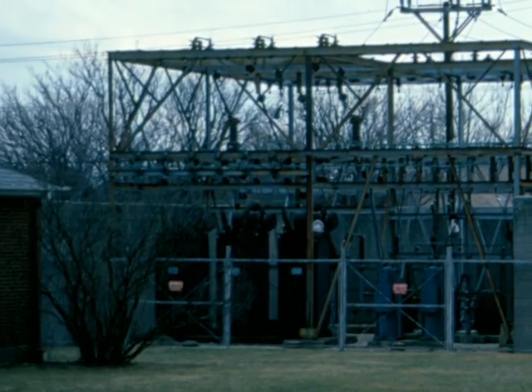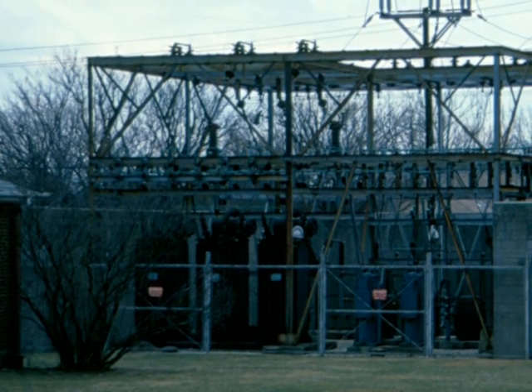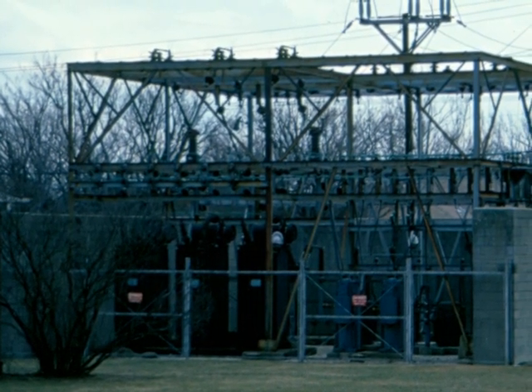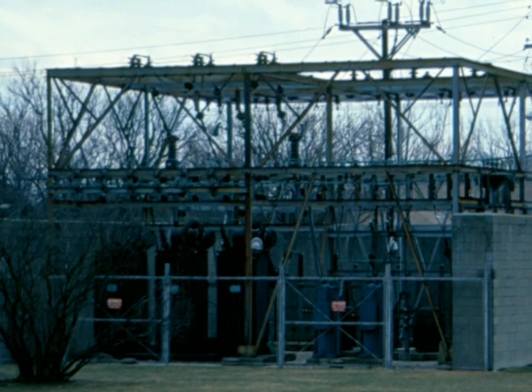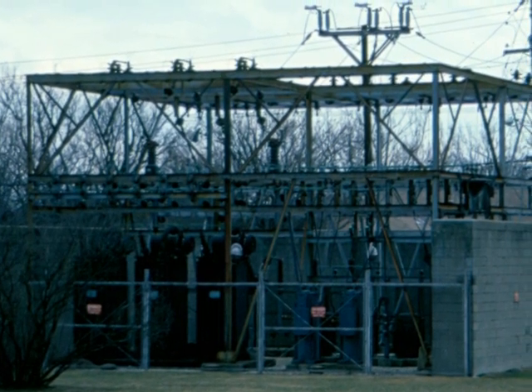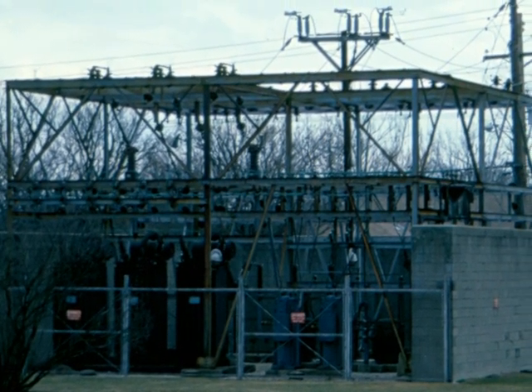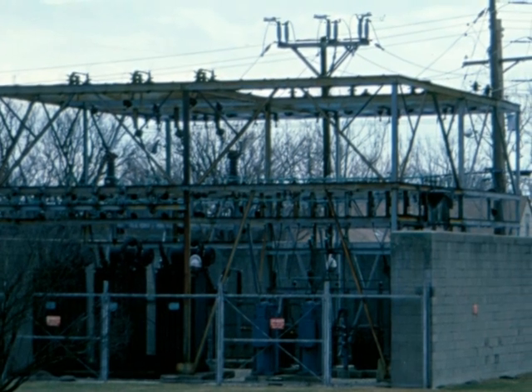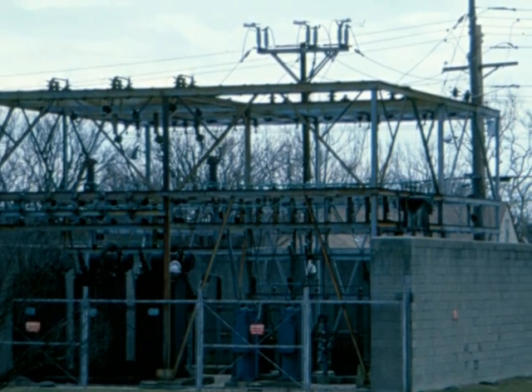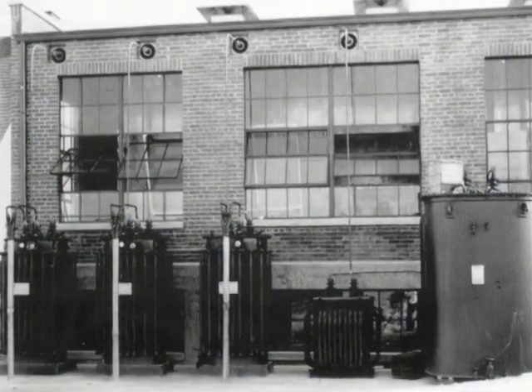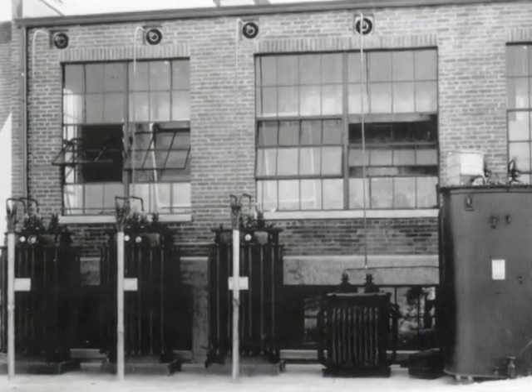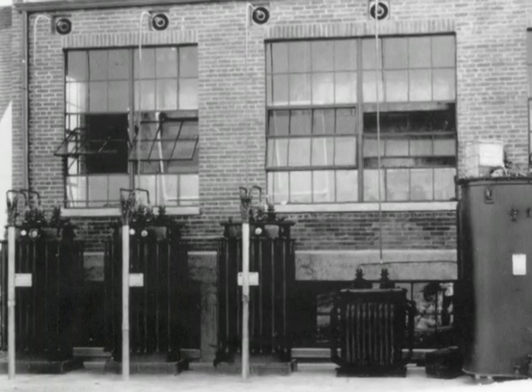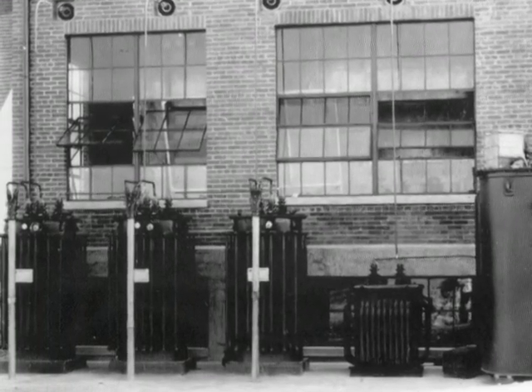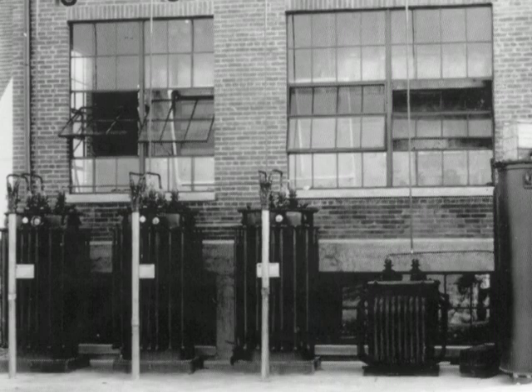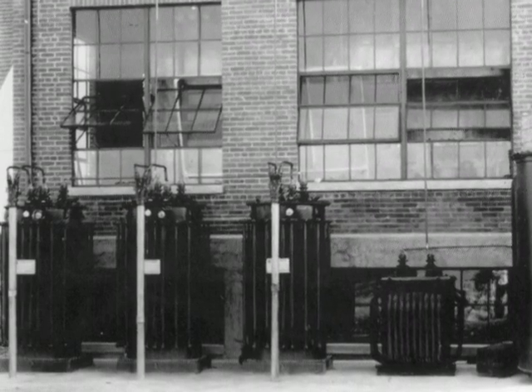Primary power was supplied to the transmitter site by 2 separate 32,000-volt circuits, one from the east and one from the west, to assure uninterrupted service. This substation transformed the voltage to 2,300 volts, which was fed underground to the transmitter building. 3 power transformers of 430 kVA were controlled by large breakers, so their primaries could be connected in a Y formation for startup and a delta formation for full power.